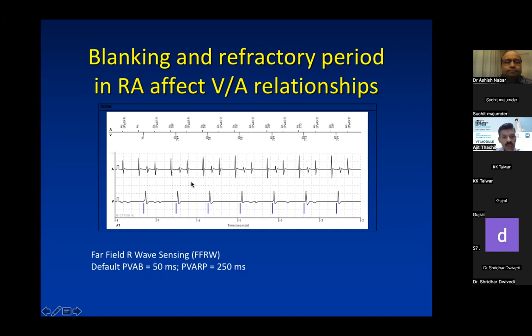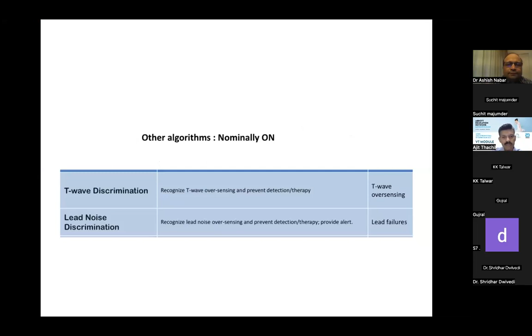So to prevent that, there is something called post-ventricular atrial blanking, which means that any event in the atrial channel which falls within 50 milliseconds after the ventricular event will not be sensed. And if it's more than 250, it will be sensed. So this can cause a problem.